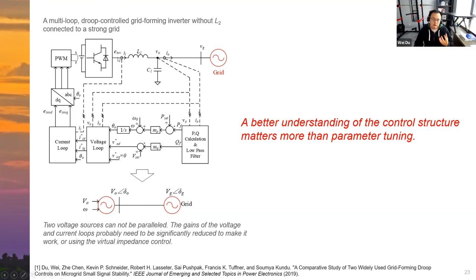If we have this grid forming inverter with only L1, no L2, and then apply the multi-loop droop control, you can see that at the fundamental frequency it's like an ideal voltage source connected to an ideal voltage source, because if we assume this is a strong grid, it's also an ideal voltage source. From very basic circuit theory, you know this will not work, because two voltage sources cannot work in parallel.